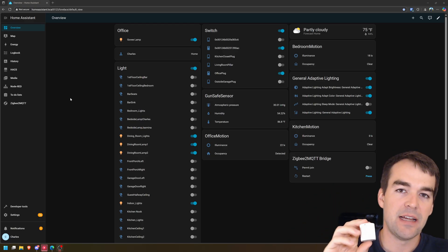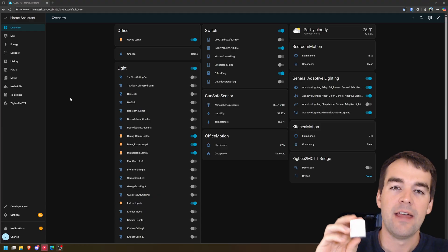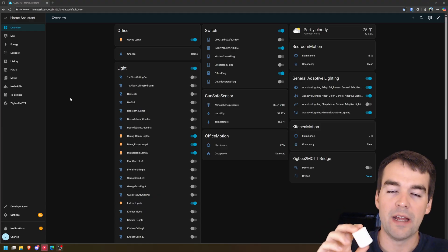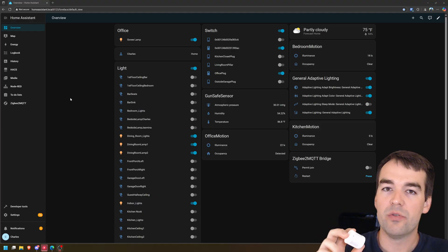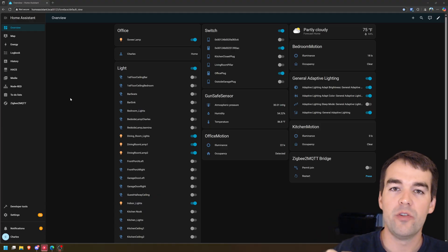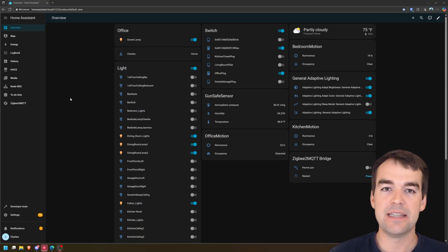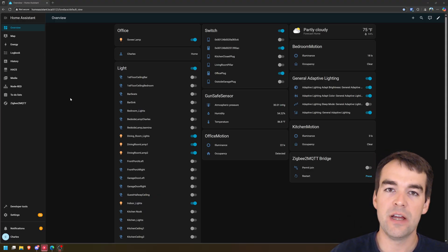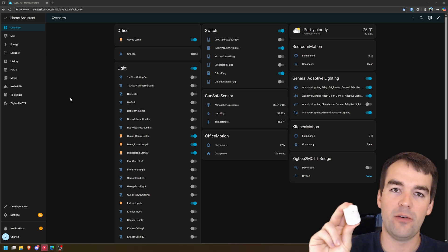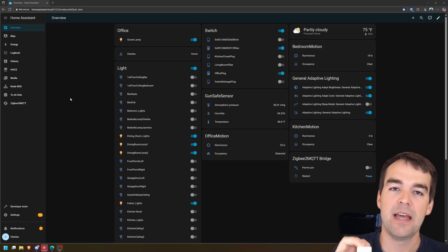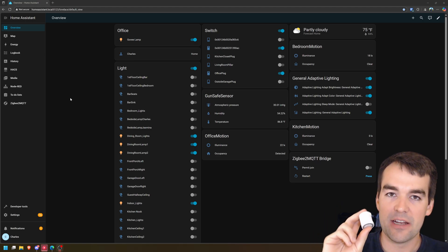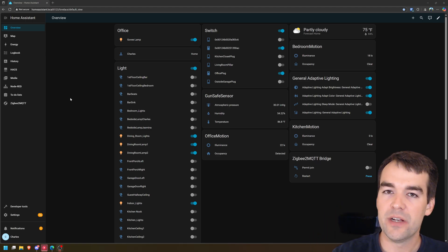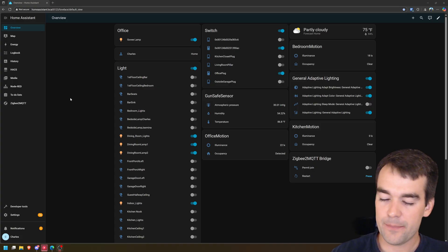There is a downside to PIR that it can only see you while you're moving. When you walk into a room, while you're moving around, if you're animated, it's going to see you. But if you're sitting dead still, it will stop seeing you. And there's a 90 second timer by default built into these that it'll say that you're no longer there. We have a little bit of logic we can add to help with that.